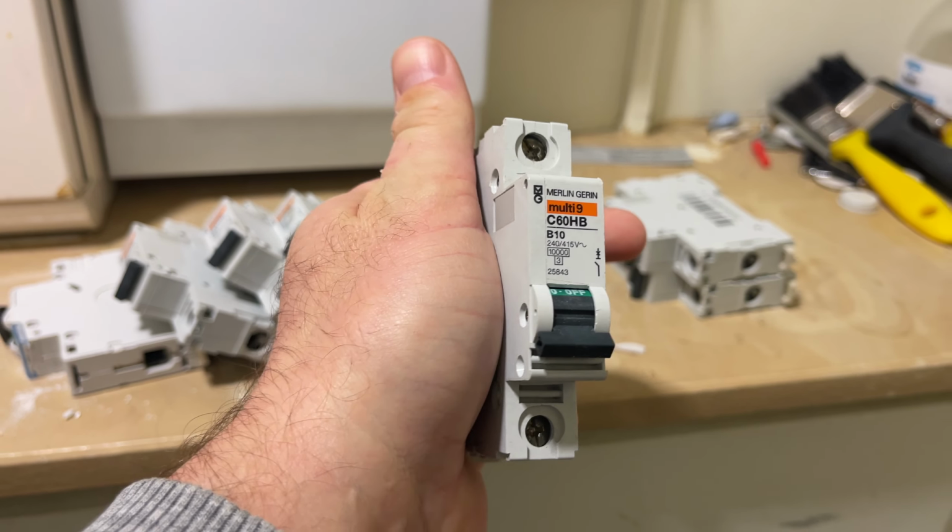We get into one of the reasons why electricians charge so much. They keep people safe. It's easy to think that DIY will save me a ton of money, right? But come on. This rating of 10 amps is not the overcurrent rating, but the rating that the breaker is designed to be able to handle in normal operation. Different breakers handle transient overcurrent, or in English, current spikes, differently. Our device has a fusing factor of 1.6. That would mean that it would take 16 amps for the device to definitely cause the breaker to operate.